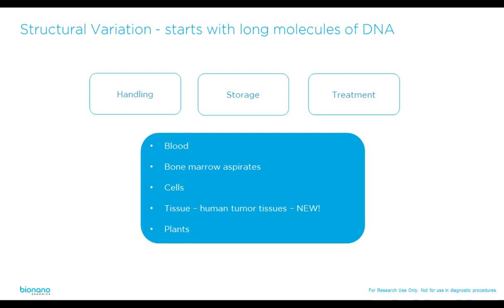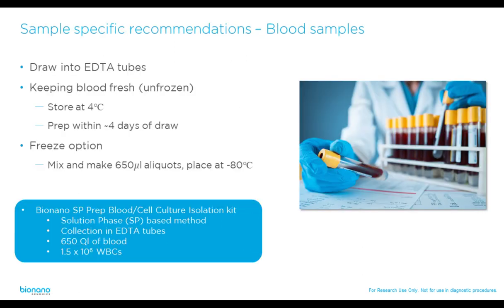Here are two tubes with black magnetic disks in them. The DNA precipitates out of solution and binds magnetically to the disk, creating white wisps attached to the disk — resembling cobwebs. It can all be washed as one unit and then transferred to a new clean tube. Sample types currently supported include whole blood, bone marrow aspirate, cultured cells, tissue using SP, and plants using agarose plug-based workflows.